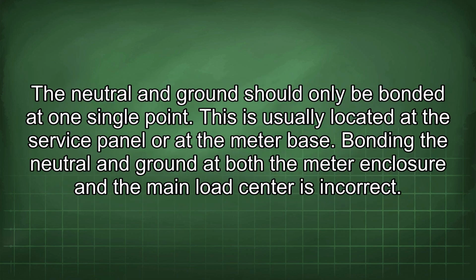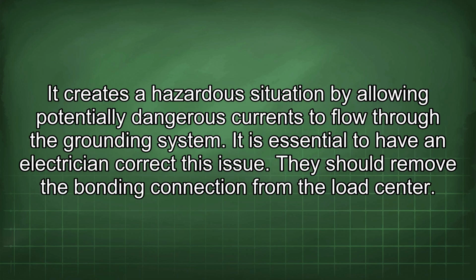The neutral and ground should only be bonded at one single point. This is usually located at the service panel or at the meter base. Bonding the neutral and ground at both the meter enclosure and the main load center is incorrect. It creates a hazardous situation by allowing potentially dangerous currents to flow through the grounding system.